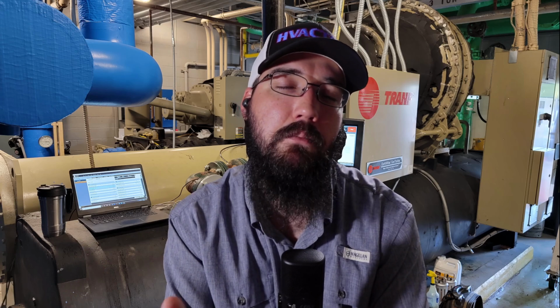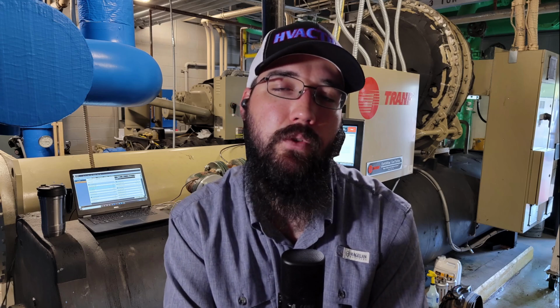You'll get that open pulse especially. So let's say it was able to make fully closed, but then you'll get that pulse open. And let's say this was a 60-second valve. Well, in a calibration, from what I've seen, most controllers will go a little bit more than the valve's rated time. So if it was a 60-second valve, it may do the opening process for 65 or 70 seconds, something like that, because it's calibrating, right? So we want to make sure that it can intentionally hit the full top end.